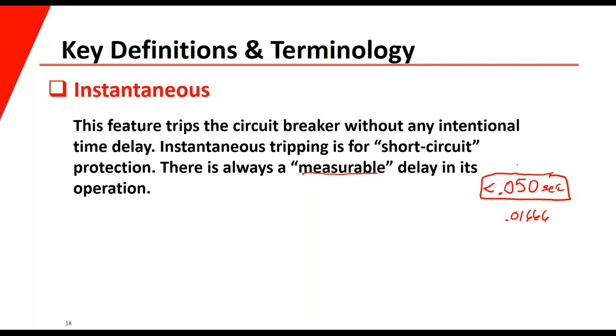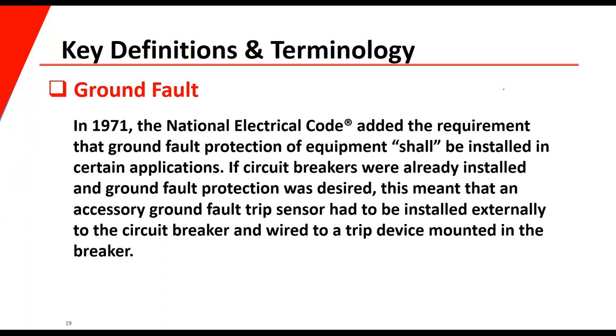You can often hear a breaker that's slow — it could be a lubrication problem. Back in 1971, the National Electric Code added the requirement of ground fault protection of equipment in certain applications. If a breaker was already installed and didn't have ground fault protection, an accessory ground fault trip sensor had to be installed externally to the circuit breaker and wired to the trip device mounted in the breaker. Most trip devices can come with the ground fault feature, but don't necessarily have to have it.